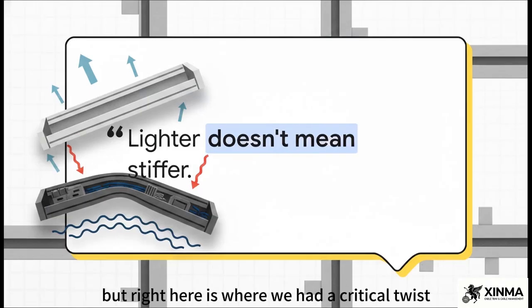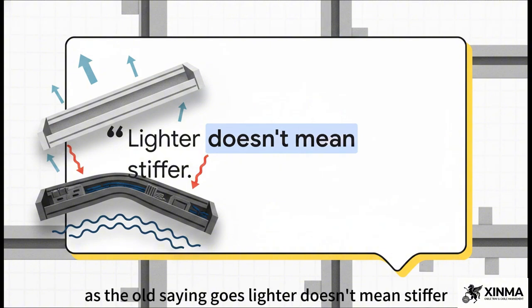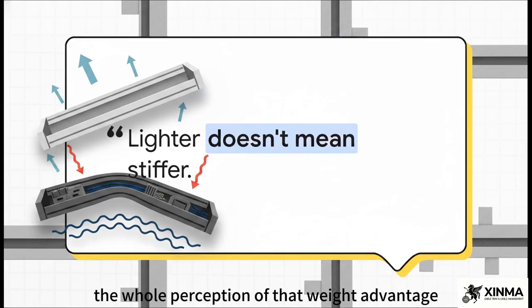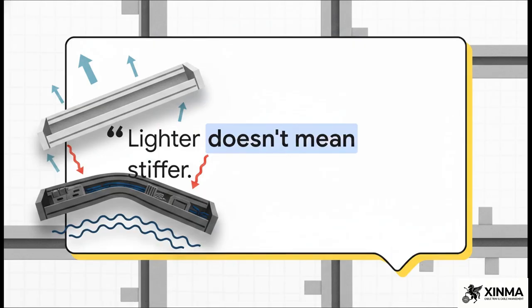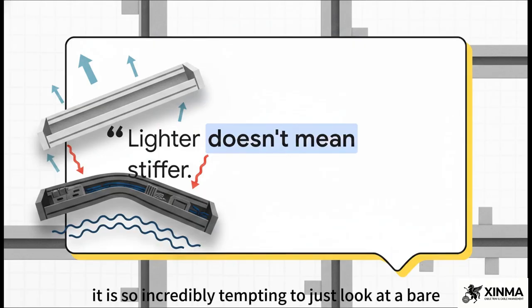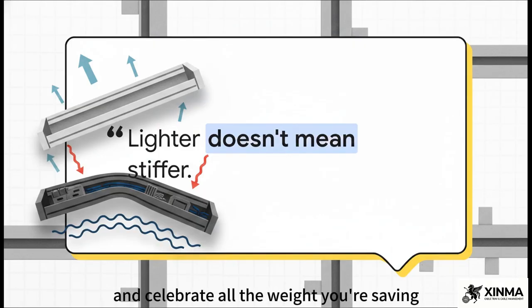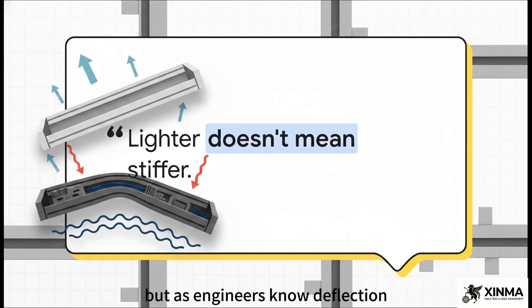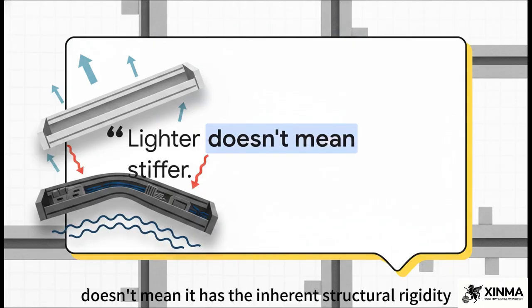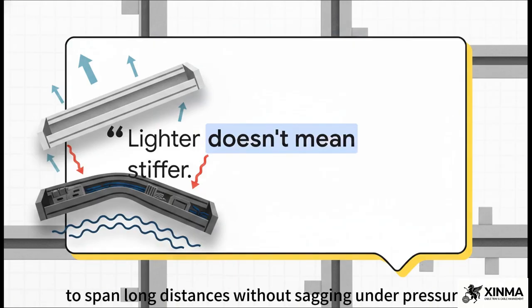But right here is where we hit a critical twist. As the old saying goes, lighter doesn't mean stiffer. The whole perception of that weight advantage flips upside down the second your cables are actually loaded into the tray. It's tempting to just look at a bare, empty aluminum tray and celebrate the weight you're saving. But as engineers know, deflection, the bowing or sagging of the tray, is the real enemy here. Just because a piece of metal is light to carry across a room doesn't mean it has the inherent structural rigidity to span long distances without sagging under pressure.